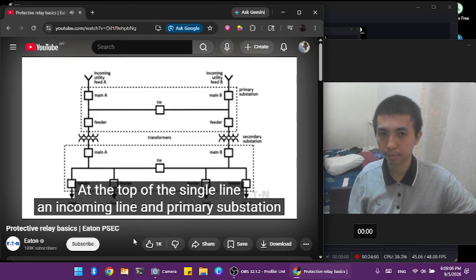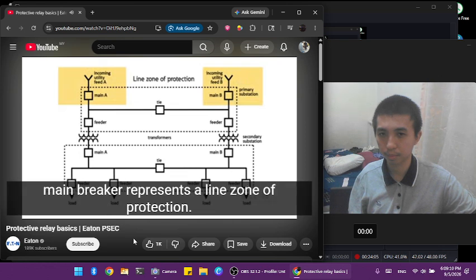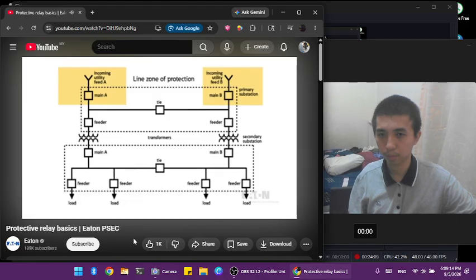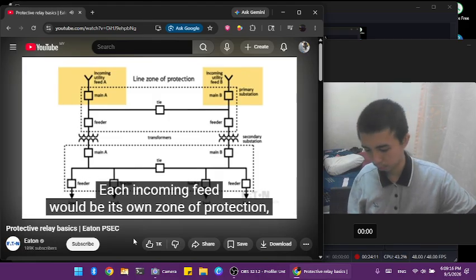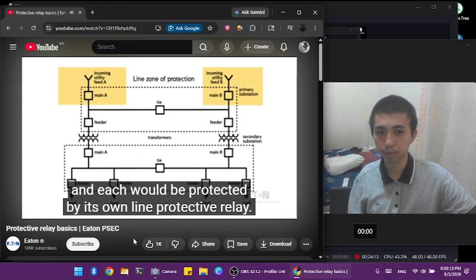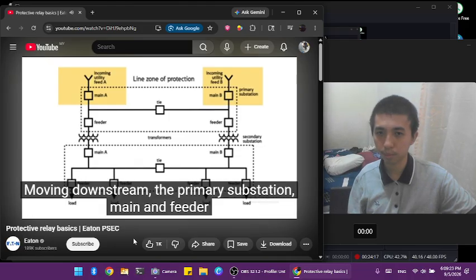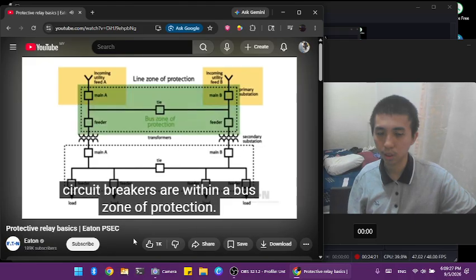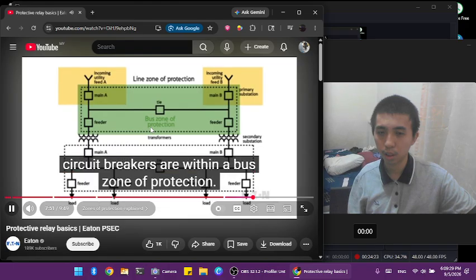At the top of the single line, an incoming line and primary substation main breaker represent a line zone of protection. Each incoming feed would be its own zone of protection, and each would be protected by its own line protective relay.